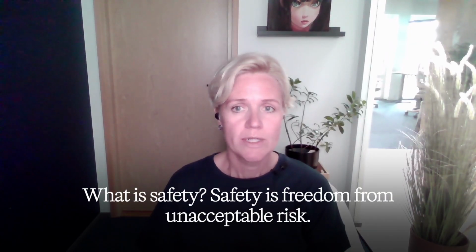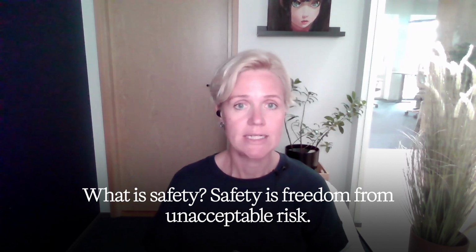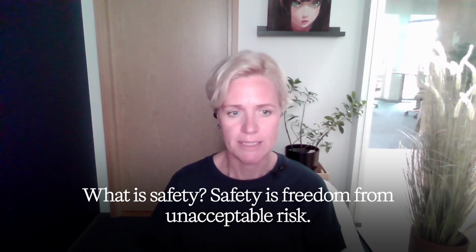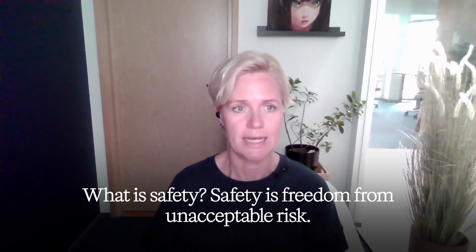In safety risk management in medical devices, you basically have two standards that you need to follow. It is the ISO 14971. And in case you're developing software as a medical device, you need to definitely look at IEC 62304. But let's start from the beginning. What is safety? Safety is freedom from unacceptable risk. And that is the main requirement from the standard, that your device would be safe to use.